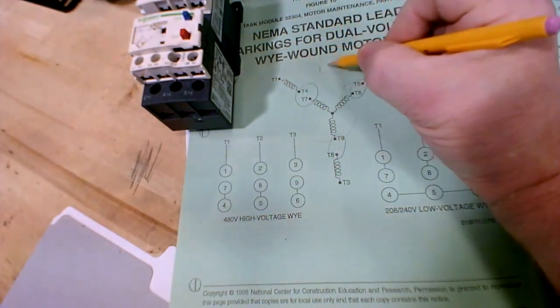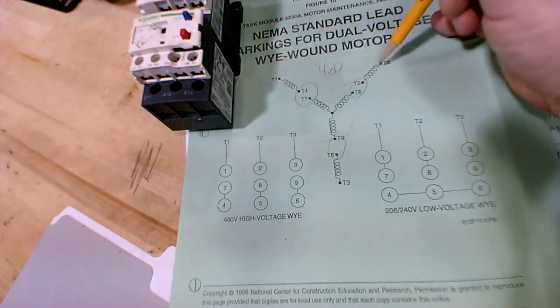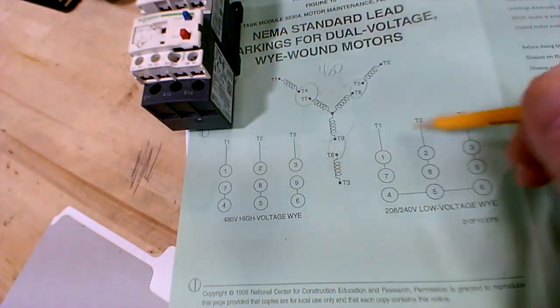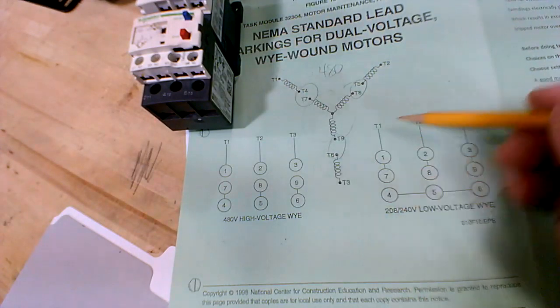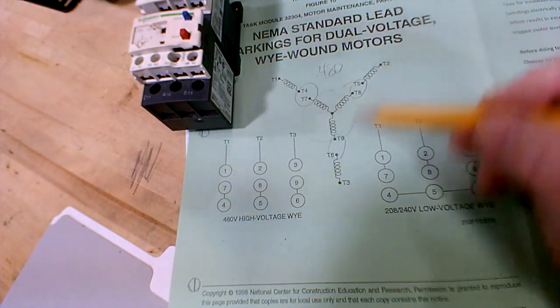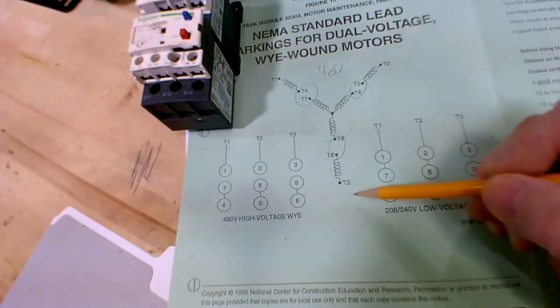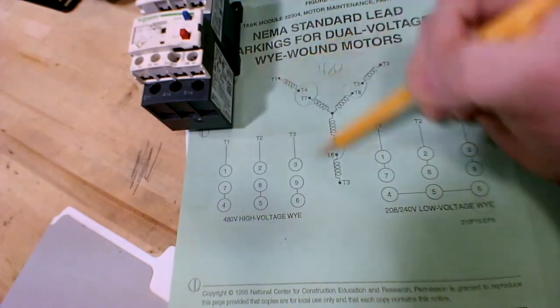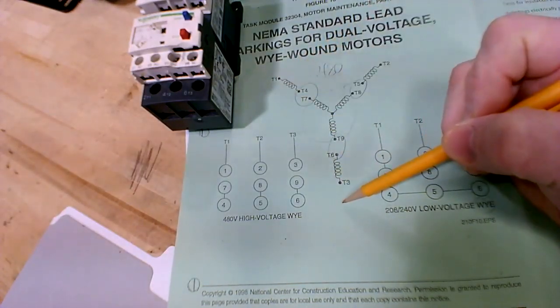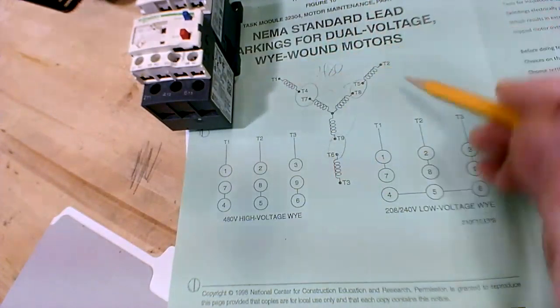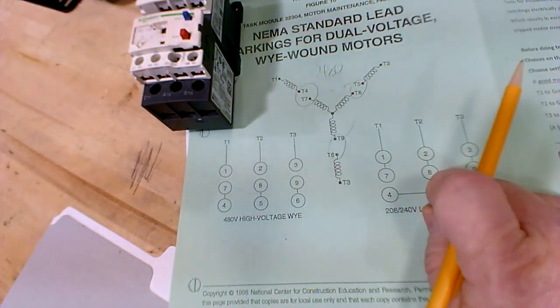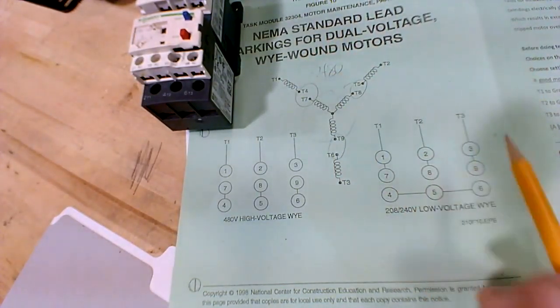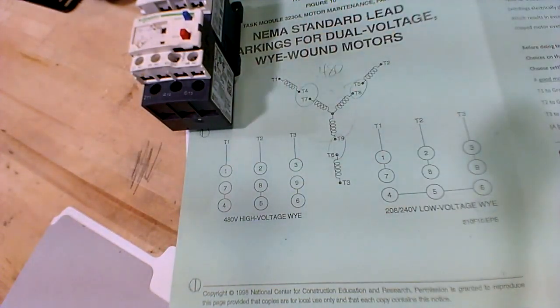So if you measure with a voltmeter between T1 and T2, you'll measure 480 volt there. If you measure between 2 and 3, you'll measure 480 volt. If you measure between 1 and 3, you'll measure 480 volt. And the windings are in series, not parallel. And you say, well, maybe the motor would run twice as fast or have twice the torque? It would not. I'm going to show you why that is.